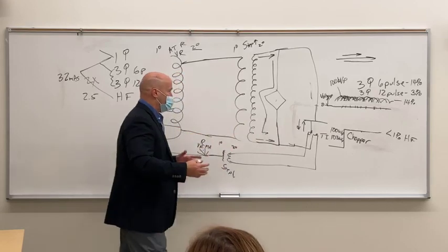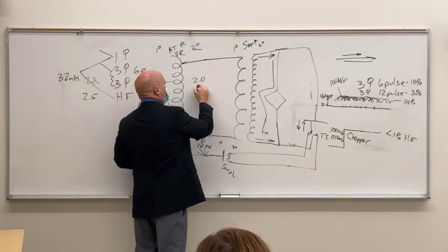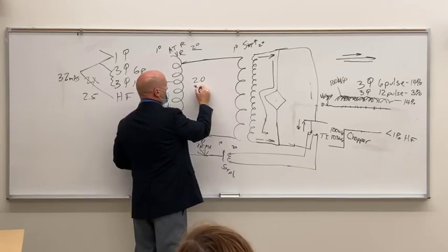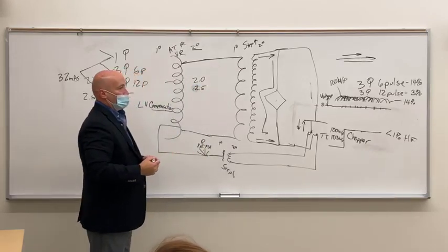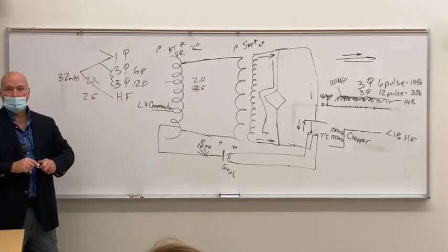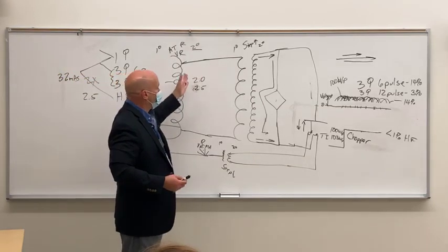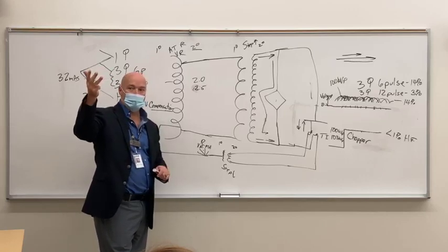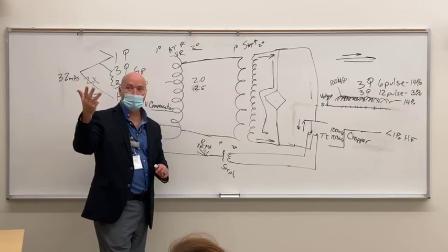Now I did all that to run through this. So 2.0, that's your factor from single phase to three phase, to 2.5. What's the difference numerically between that? It's 0.5, right? But how many 0.5s do we have in 2? 0.5, 1, 1.5, 2. Right? So there's 4 of them, right?